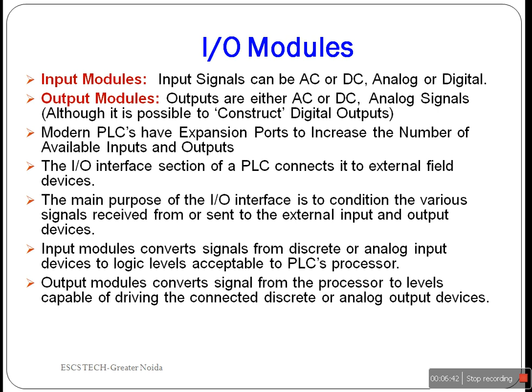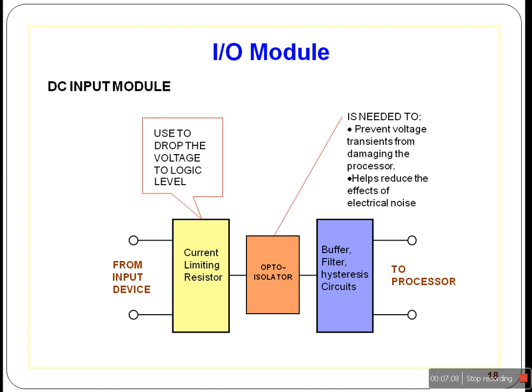Here is the input signal conditioning circuit block diagram for the DC input module. The current limiting resistor is used to drop the input voltage to logic level, and the opto isolator provides isolation as it prevents voltage transients and electrical noise. The buffer is used to prevent loading effect, and the filter and hysteresis circuit remove the noise.